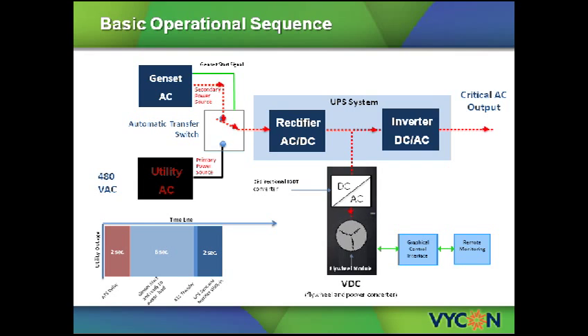Now, with the UPS rectifier fully energized, providing power to the DC bus, the flywheel energy storage system will start recharging, again converting electrical energy to kinetic stored energy. The recharge time for the flywheel can be between 2 and 15 minutes depending on the depth of the discharge and the recharge current setting on the system.